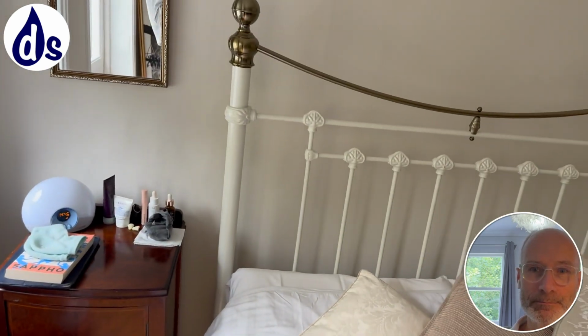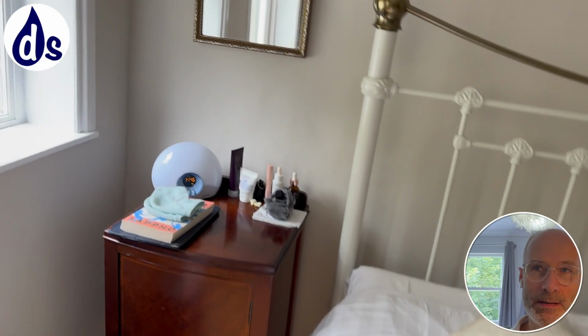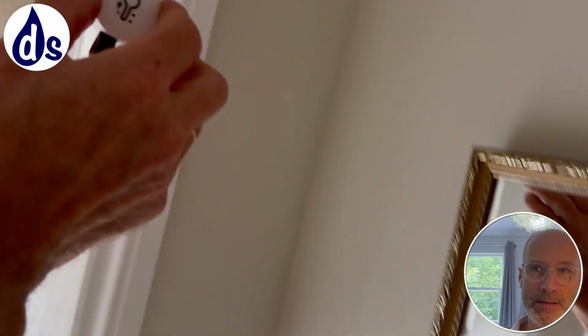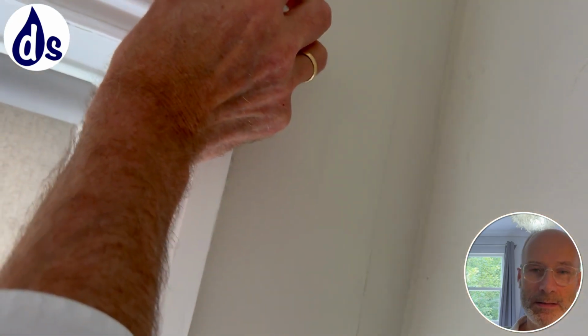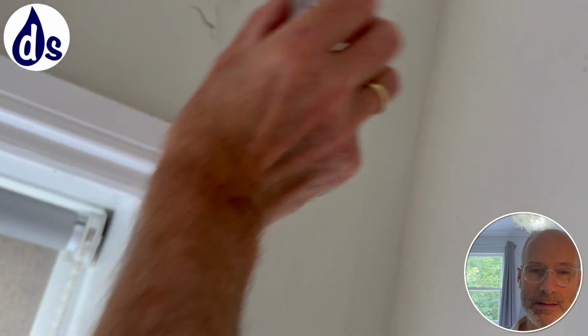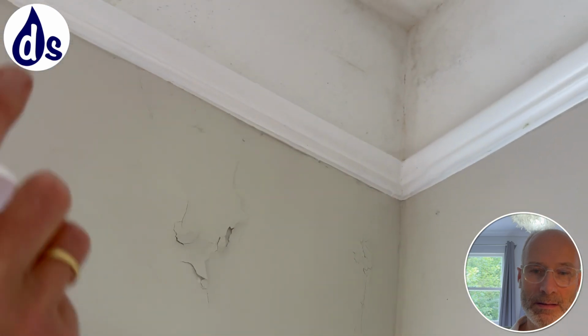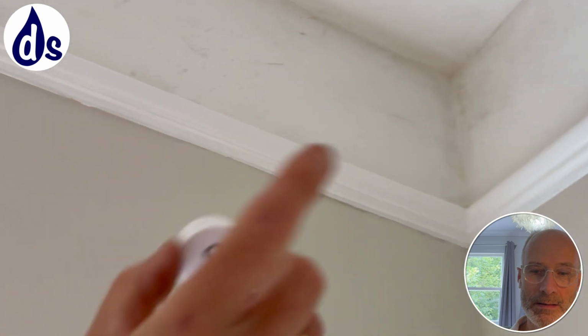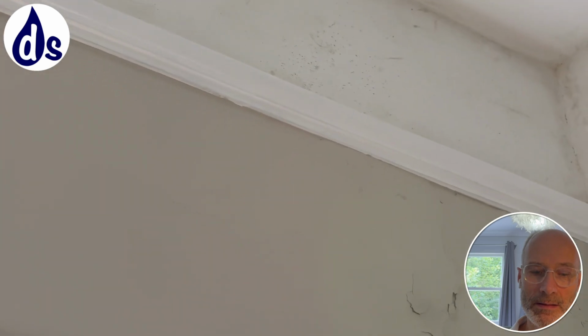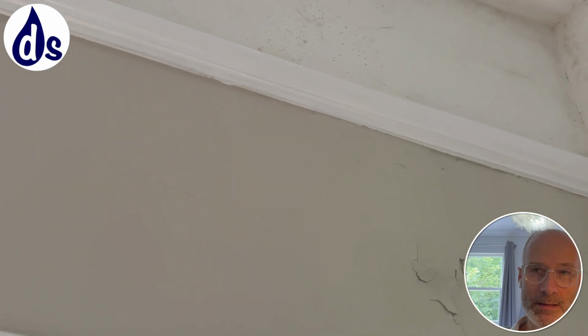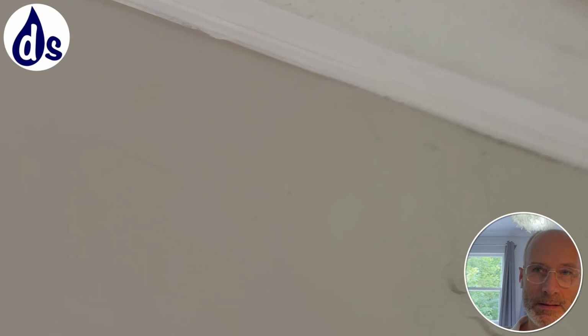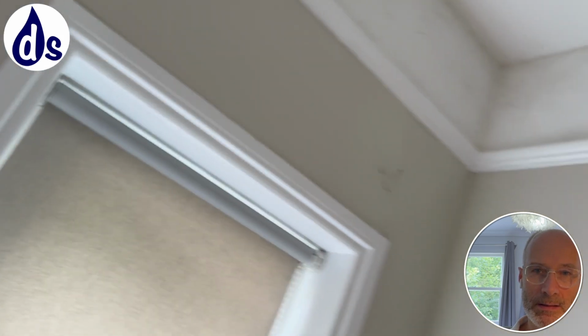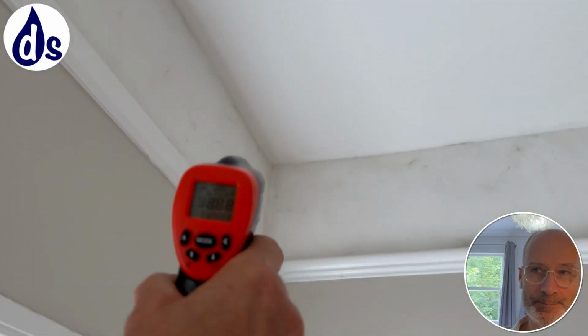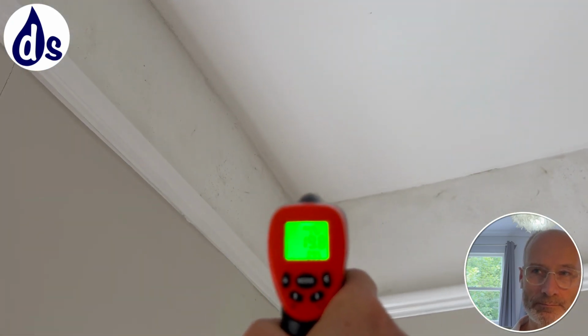So with the data loggers, when you've got the data loggers up, you want to have it close to a damp zone, but it's hard to get it right in the corner. You've also got a bit of mold growing up there, which again is a sign of high excess humidity. It grows where relative humidity is above 85% for a long period of time. But it's very difficult to get it at the coldest point. You can use something like a laser thermometer to find the coldest point.